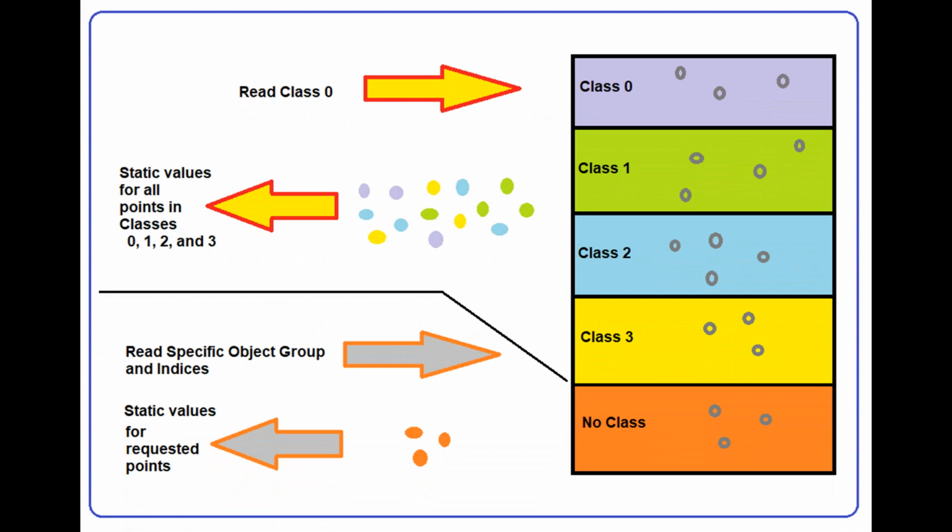And the second point refers to no class. As we previously stated, there are 4 data classes, 0, 1, 2, and 3. But there's also a 5th possibility called no class. Most input points reported by an outstation send data obtained or calculated from field inputs. Sometimes some binary or analog inputs report parametric data, which typically never changes or does not need to be reported when it does.